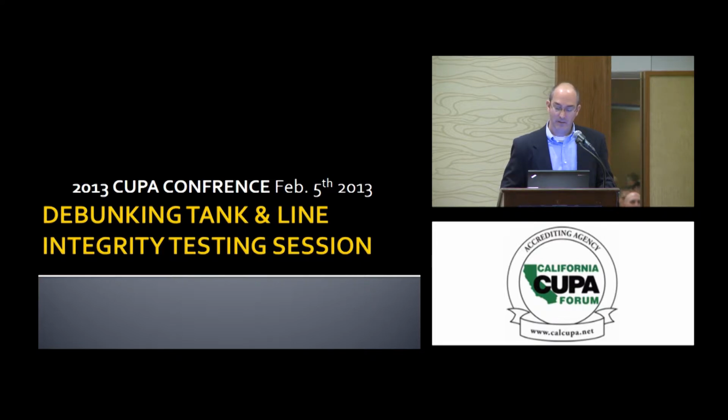This cutaway is, if you can see it, it shows kind of one of the features of the common red jacket turbine. There's an O-ring right here that could leak, and fuel would go past there during a line test and drain back down into the underground tank. Now, that's not a leak into the environment, but it would cause a failure of a line test. So we have a different methodology. It's got a little plug that comes off the bottom of here that can isolate that O-ring. So, and there are many other tricks of the trade to make sure the line is totally isolated. If all fails, the line would have to be disconnected by taking apart the piping and breaking the unions and things like that to totally isolate it from the tank and dispensers.